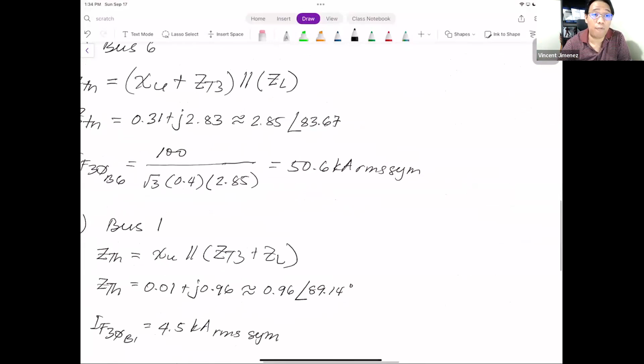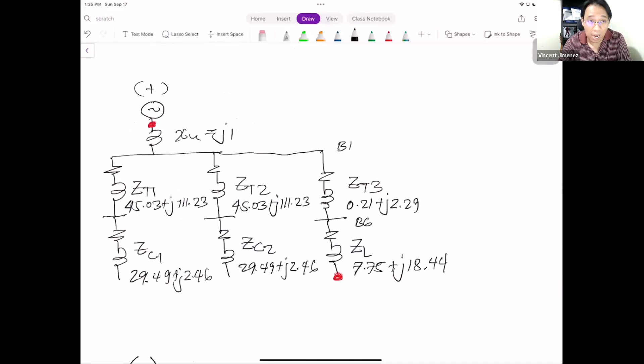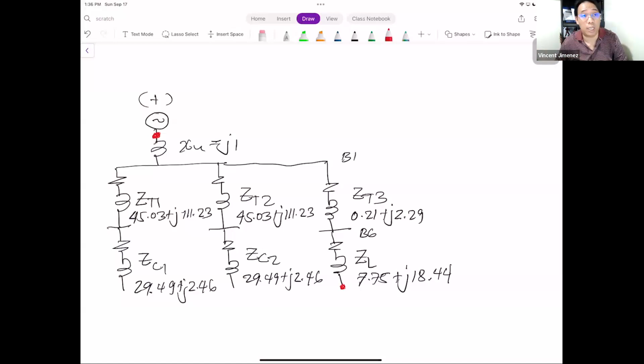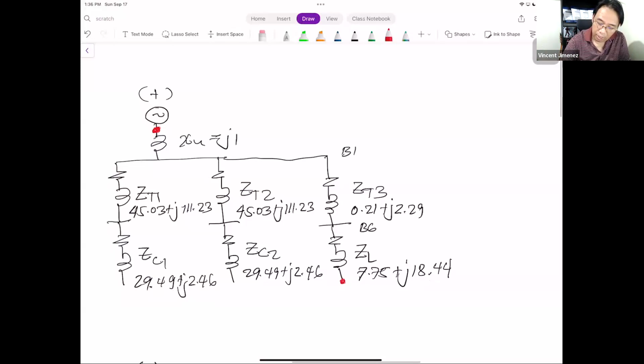At bus 6, since the three-phase load, the motors, no longer contribute, you remove that red dot. What remains going to bus 6 is the series combination of XU and ZT3. I hope that's clear. There is no contribution because it is already 30 cycles. Motors contribute only up to 2 cycles; after 1 to 1.5 cycles their contribution is gone. IEEE recommends the 30 cycle calculation for the minimum fault. So what remains is just the utility. XU is in series with ZT3.